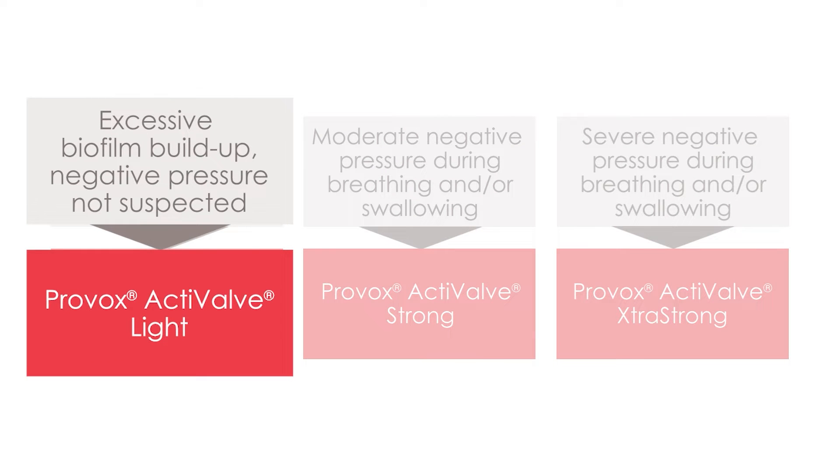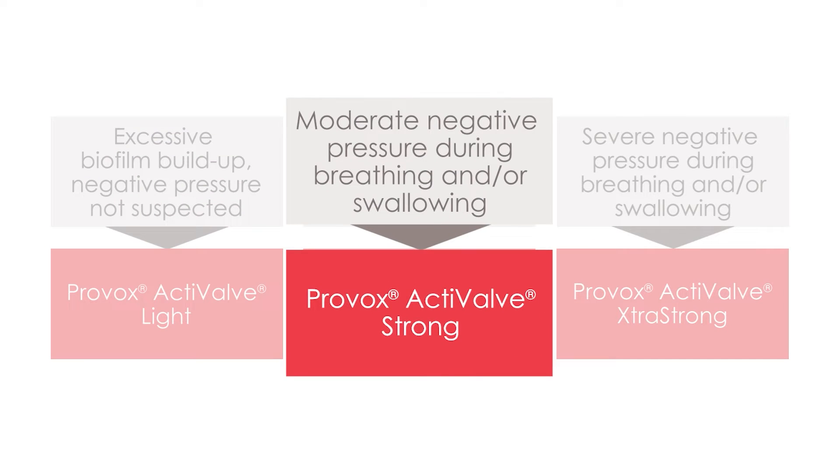If short device life is due to excessive biofilm buildup and negative pressure is not suspected, then start with the Provox ActiValve Light. If short device life is due to suspected negative pressure resulting in inadvertent active valve opening during breathing or swallowing, with or without biofilm, then begin with the Provox ActiValve Strong.